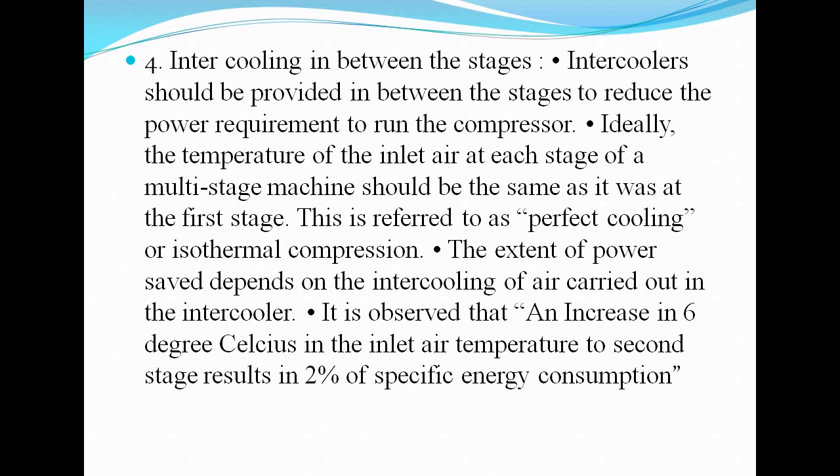An intercooler should be provided in between the stages to reduce the power requirement to run the compressor. Ideally, the temperature of inlet air at each stage of a multi-stage machine should be the same as it was at the first stage.